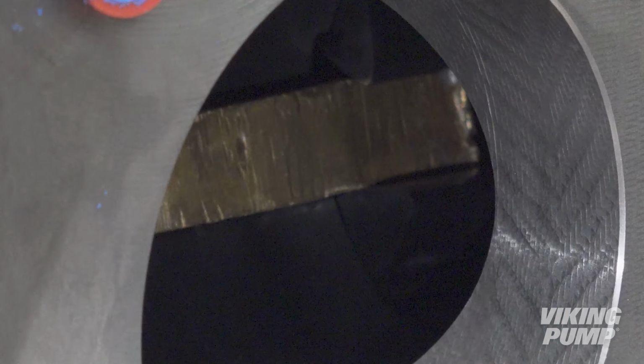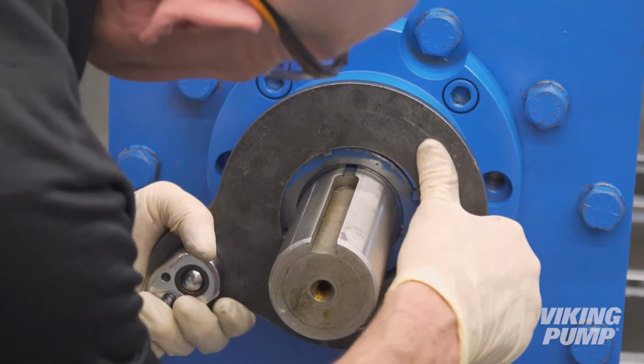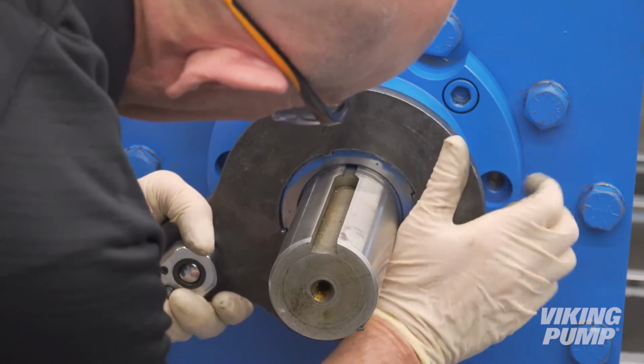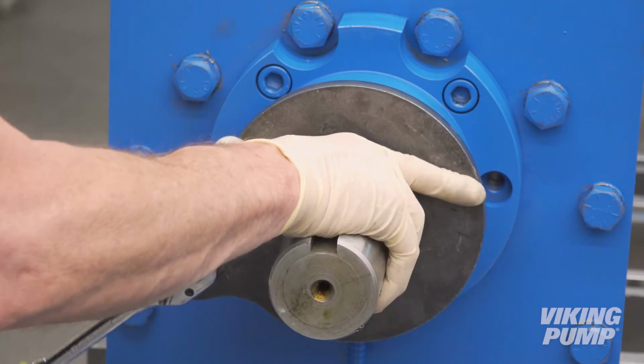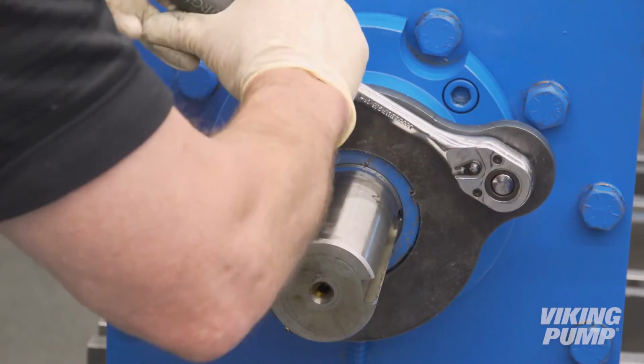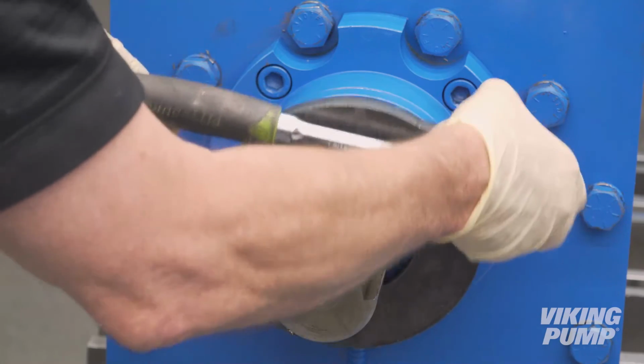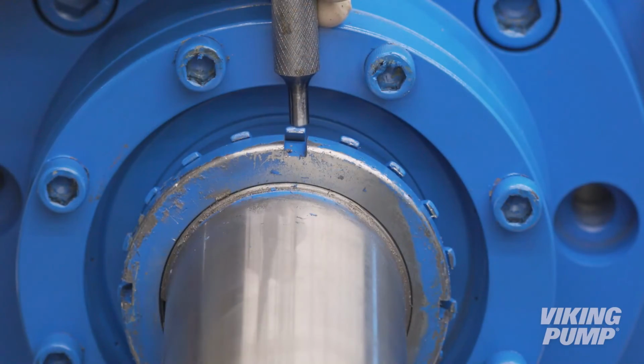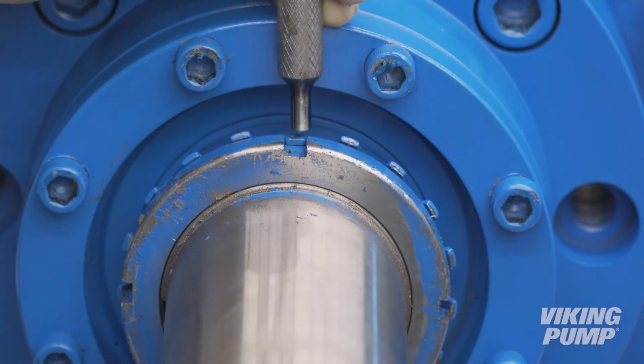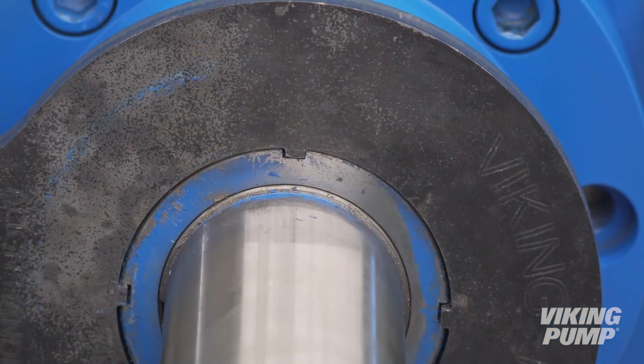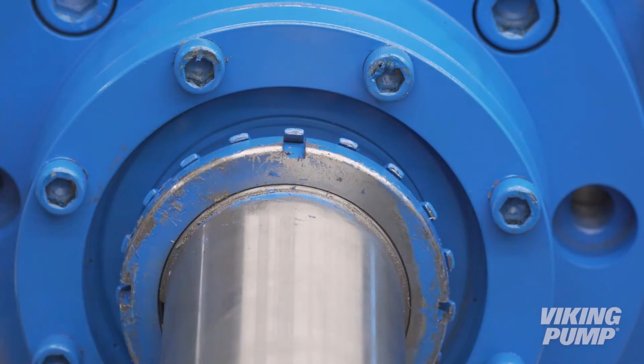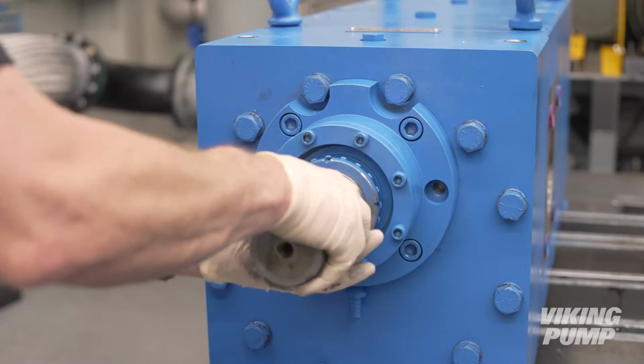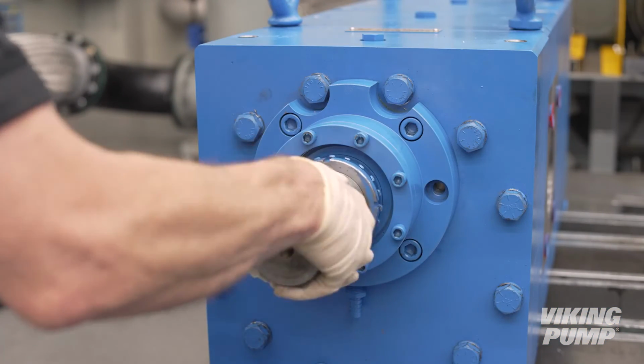Insert a brass bar or piece of hardwood through the port and between the gears to prevent the shaft from rotating. Using the provided lock nut tool, torque the lock nut to the appropriate torque setting. This value can be found in the technical service manual. Finally, bend a tang of the lock washer that aligns with the groove of the lock nut. If no tang aligns, tighten until one does. Finally, turn the shaft manually to ensure the pump rotates smoothly.